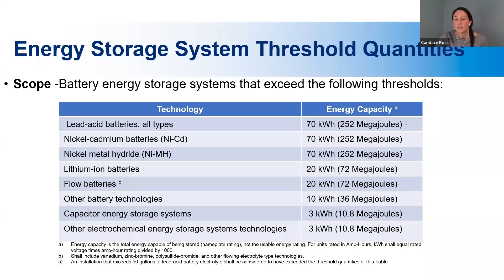These are the energy storage system threshold quantities. It goes through the different technologies, and if the energy capacity of a single module exceeds these thresholds, it will need to go through the fire code and meet all these requirements. So once again, these are mostly those commercial utility size systems.